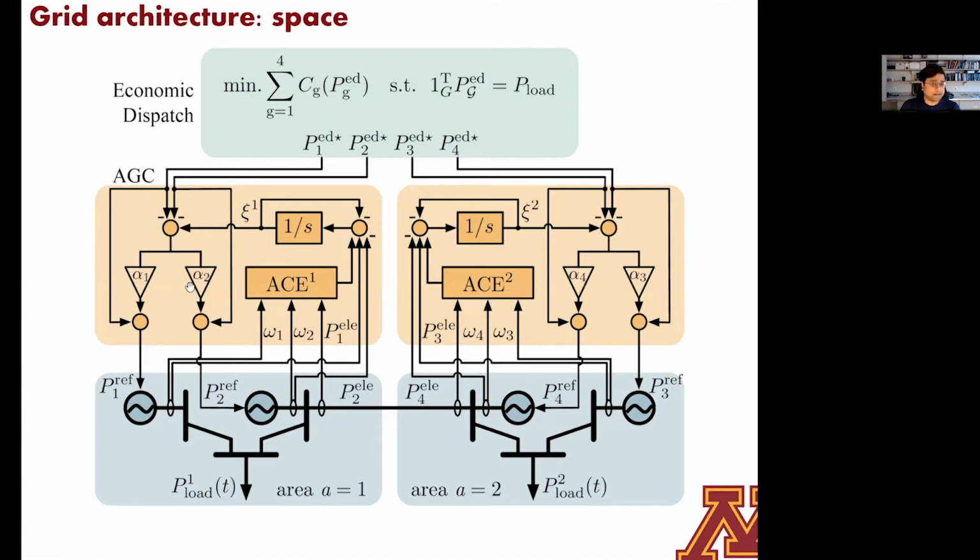Again, there are a couple of feed forward gains here, these alpha terms, which we'll see become important. And this is just a way of allocating the net additional load that you haven't forecasted across all the generators to zero out this area control error on an area by area level. So at the end of the day, you're able to regulate frequencies to where they need to be. An added effect of this is you're also able to regulate flows on these key tie lines that go across control areas to what they have to be scheduled.